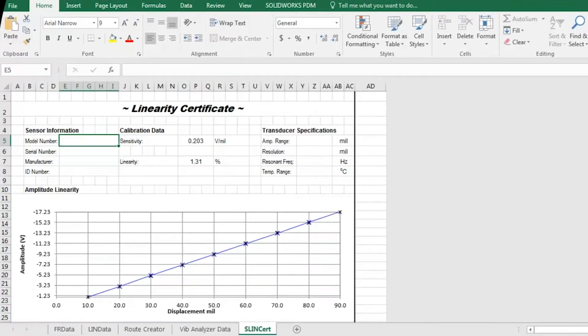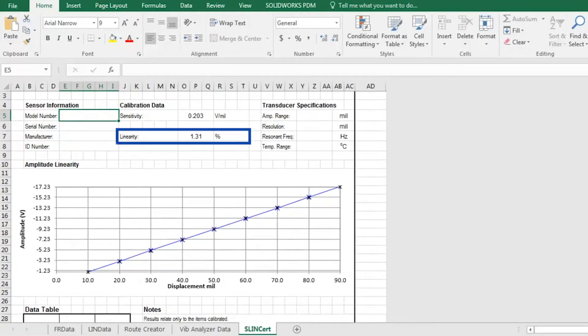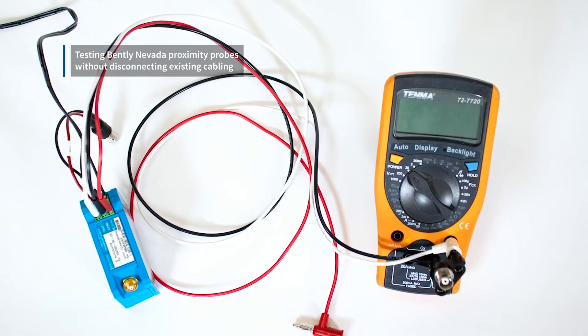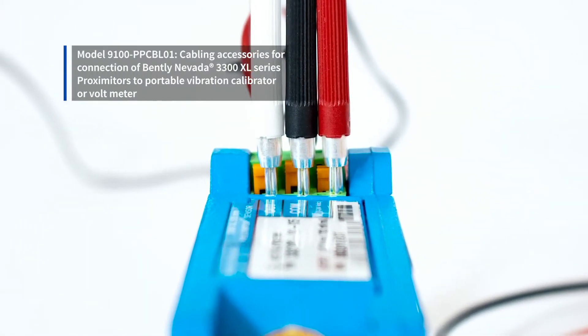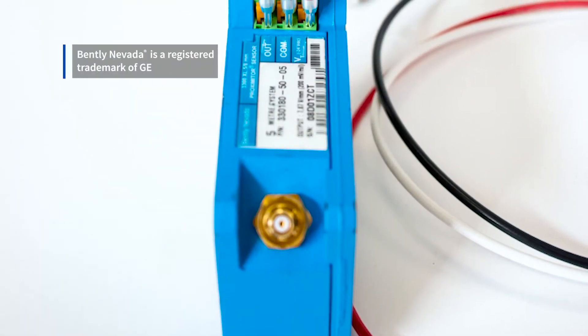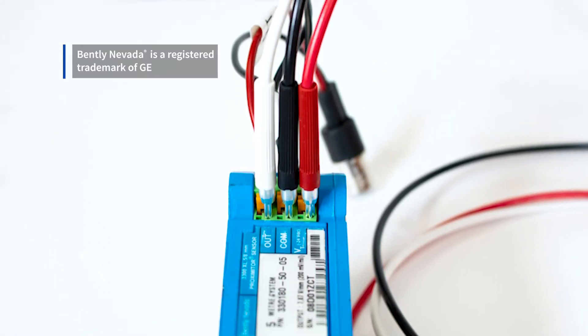I press view certificate in the report generation workbook that is supplied with the 9110-D, and you can see that our sensitivity was 203 millivolts per mil with a maximum nonlinearity of 1.31. To make proximity probe testing easier, The Modal Shop supplies model 9100-PPCBL01. These are test leads that connect to the Bently Nevada Proximitor and allow you to test proximity probes without disconnecting the existing cabling. The kit comes with the test leads, a BNC to banana plug made by Pomona, and a BNC to BNC cable.